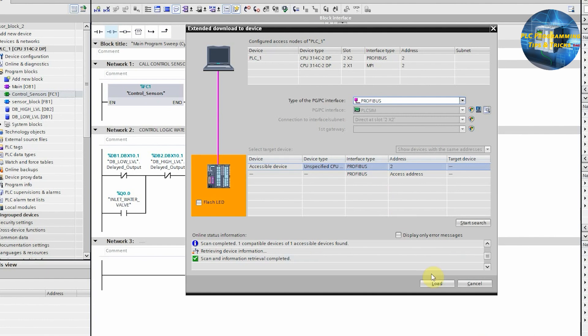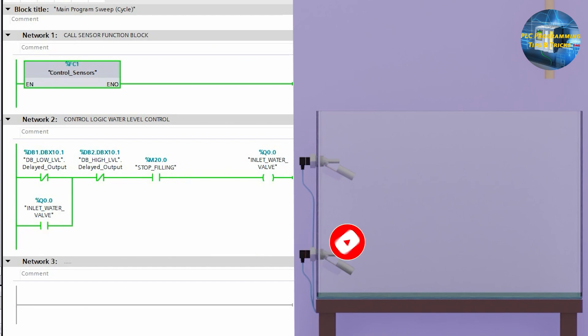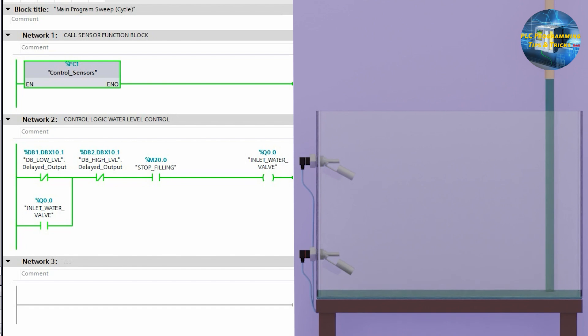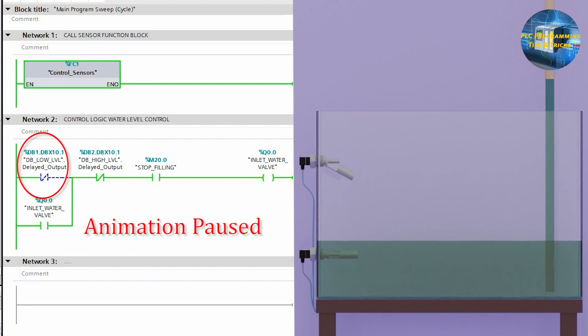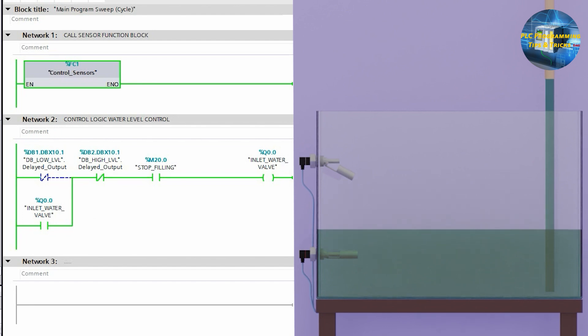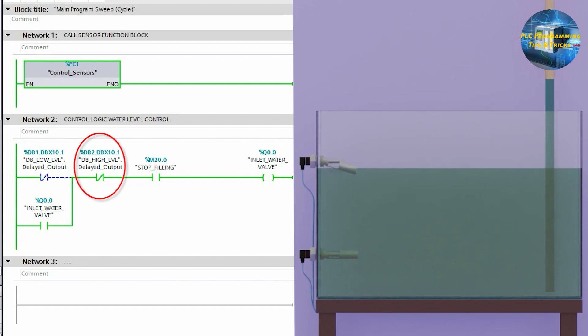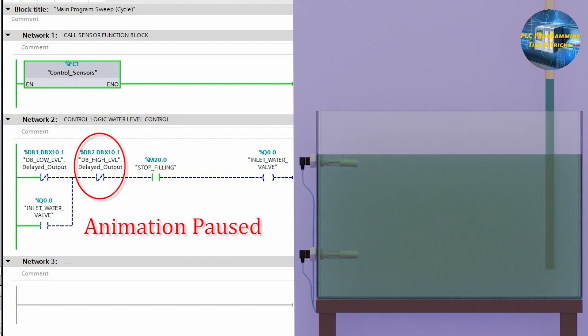We will download this logic into the PLC and go online to see how it works. As you can see, when we turn on the stop filling button, the water inlet valve turns on and water starts to fill the tank. As the water touches the low level probe I0.0, the delayed output normally closed contact opens after the delayed set point. Similarly, as the water touches the high level probe I0.1, the delayed output normally closed contact opens and turns off the water valve Q0.0.